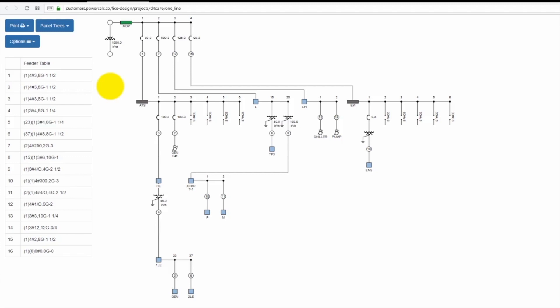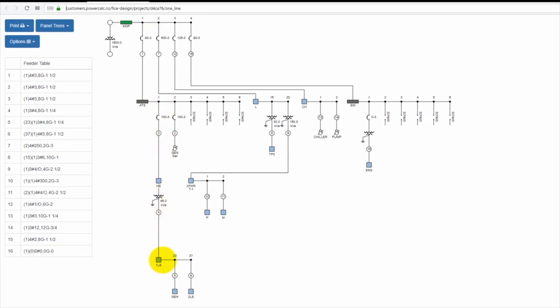Let's look at the entire power distribution system for our school, the Atlantic West Elementary School. You can see here at the top is main distribution panel, and then the power flow downstream to each of the distribution panels and the panel boards and to the equipment as was designed. The power flow from the top to the bottom which is the opposite of our concept in developing the one line diagram. When we develop the one line diagram, we develop it from the bottom up. We started from the branch circuit panels and build it up all the way until we got to the main distribution panel.